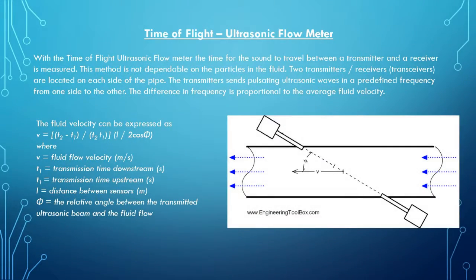With time of flight ultrasonic flow meters, the time for the sound to travel between the transmitter and the receiver is measured. This method is not dependent on the particles in the fluid. This can be used to calculate the fluid velocity using the formula on the screen and in your handout.